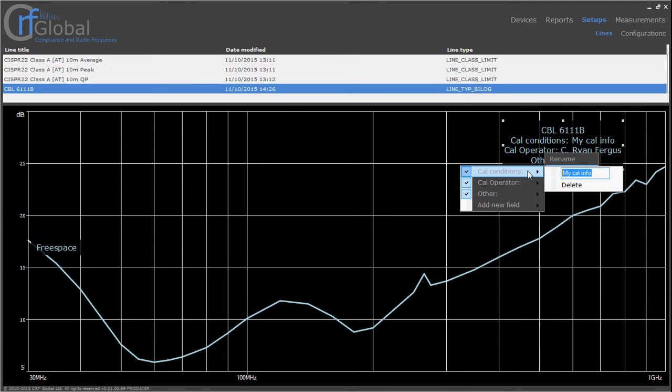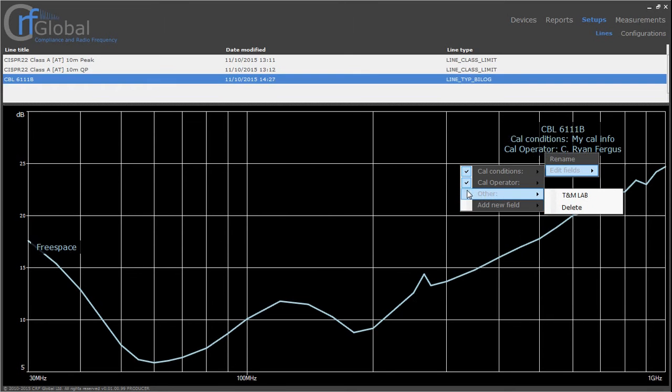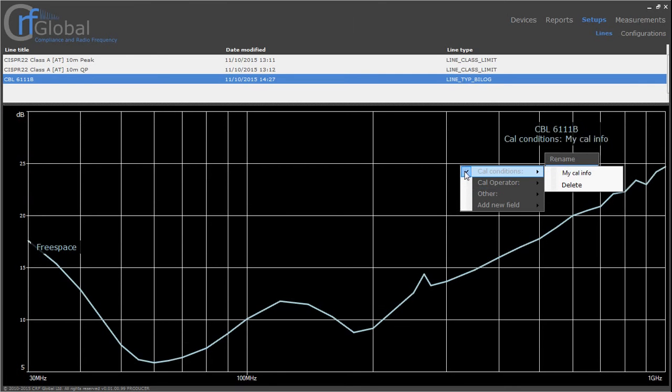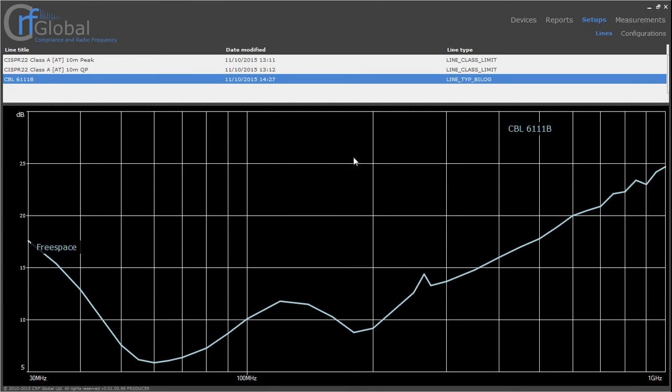There is a space for adding measurement uncertainty as well, because that can go to the configuration where it will create a bill of measurement uncertainties for you. We already had an introduction to the other fields earlier on through test and measurements. The same principle applies here. Given that we don't have any calibration information for this, I'm going to remove that.